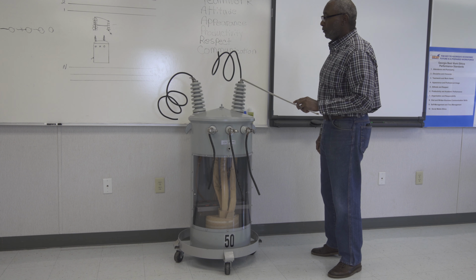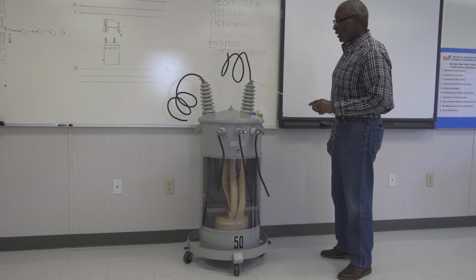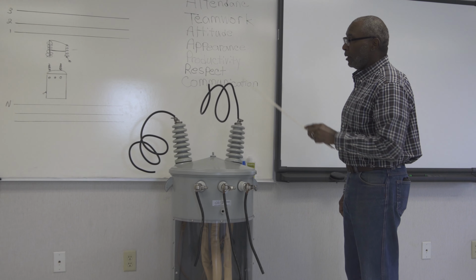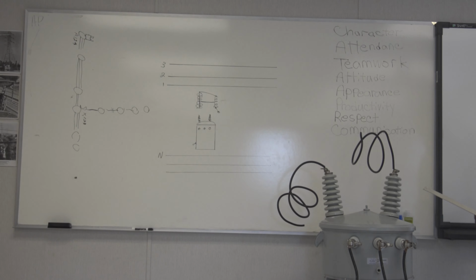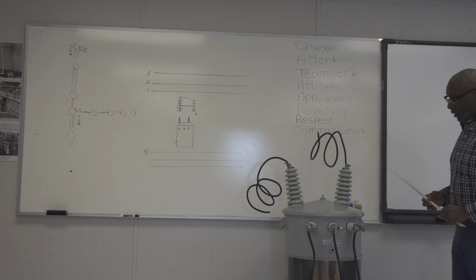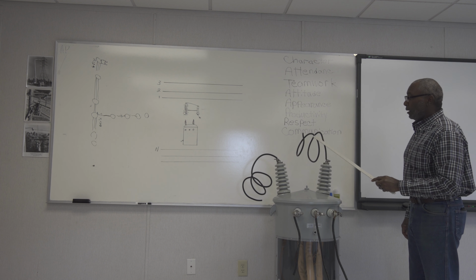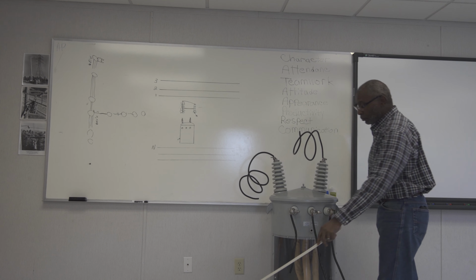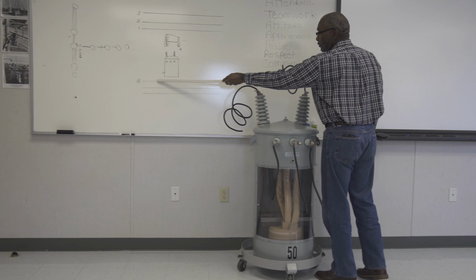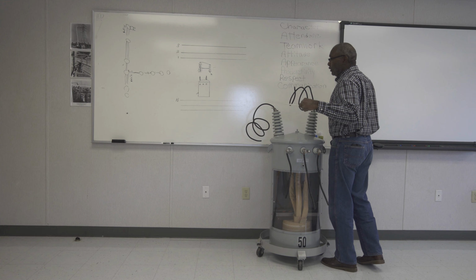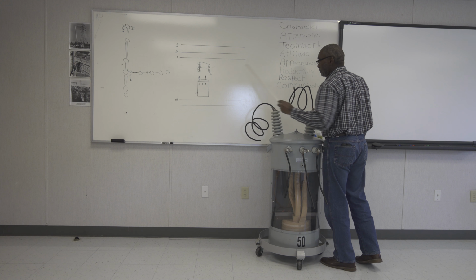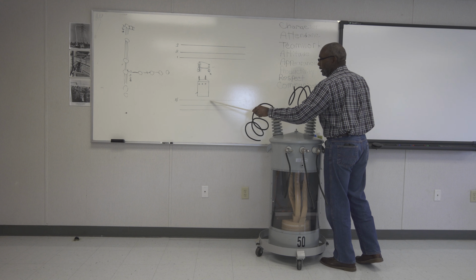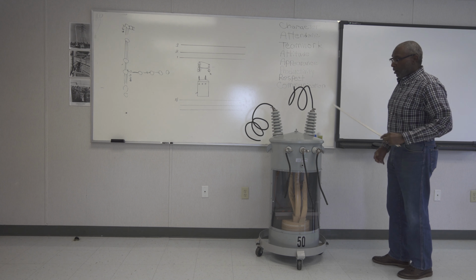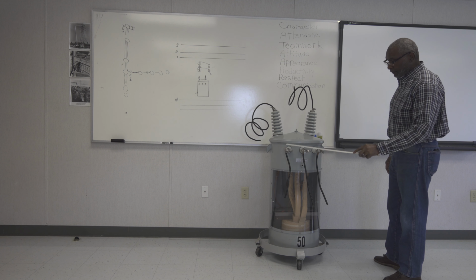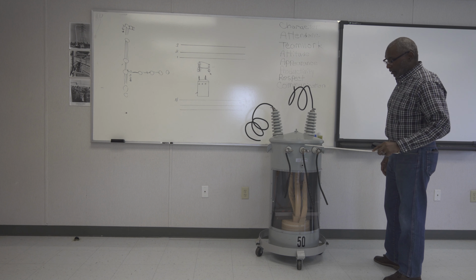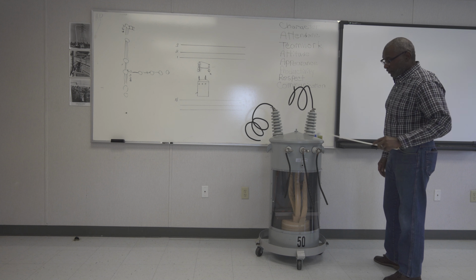You will have one of these bushings going to your switch, which I have right here, a drawing indicating the switch cutout, fuse cutout, and then the other will go down to your mainline neutral, which is right here. So this one will go here to your switch cutout. This one will come down here to your mainline neutral. On your low sides, you have readings of 120 volts, 120 volts, and together 240.